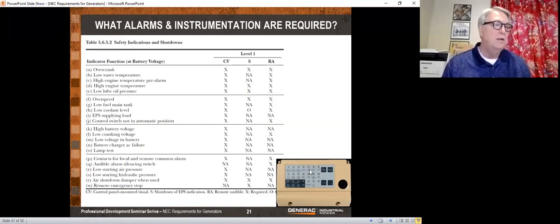So we get into trouble a lot of times. People will go out and they'll buy either a residential generator or a light duty commercial generator, which are perfectly fine. They use those on all kinds of commercial buildings, 7-Elevens, places like that, but they cannot be used as an emergency or legally required generator because they don't have this NFPA 110 controller. And this is a heartbreaker.